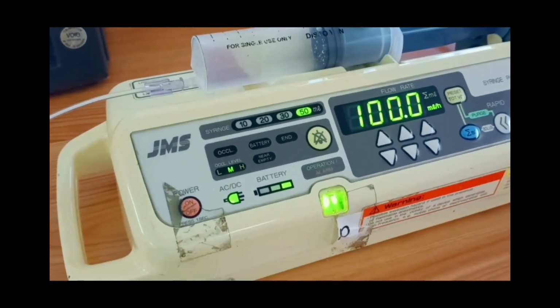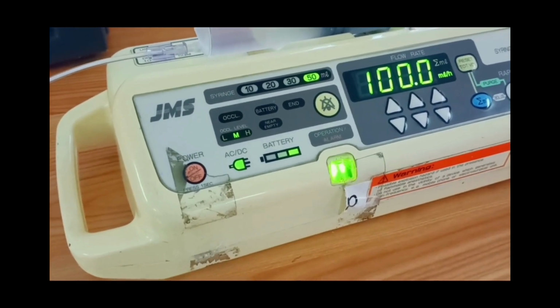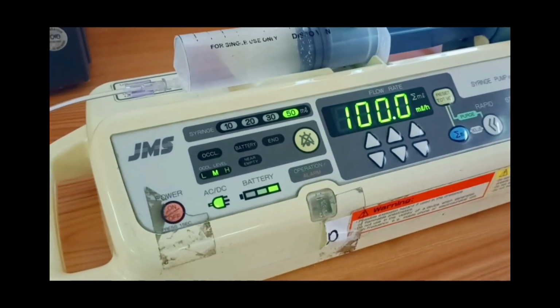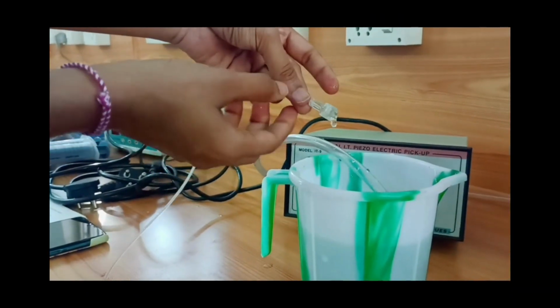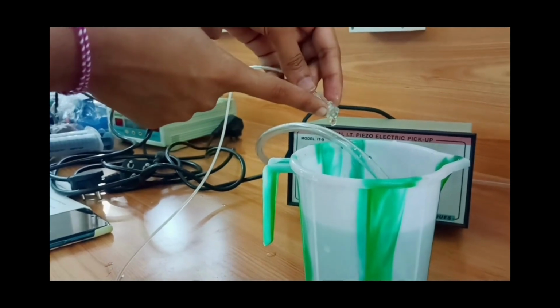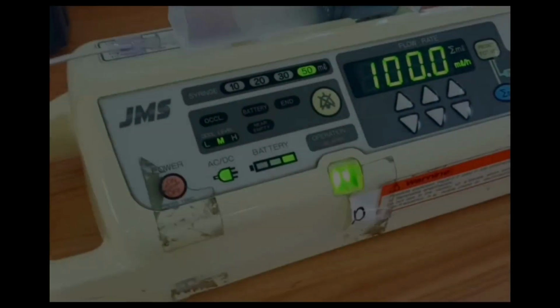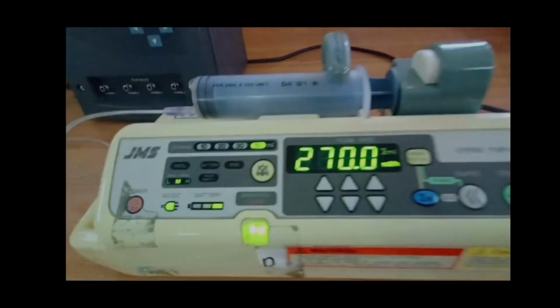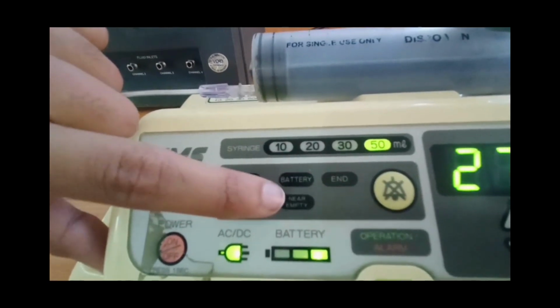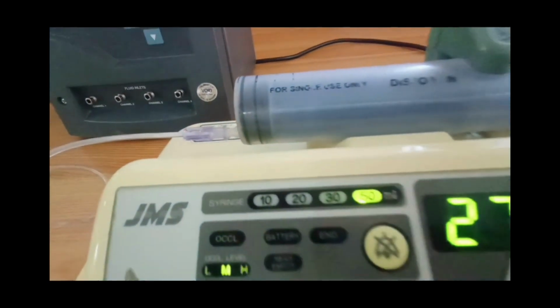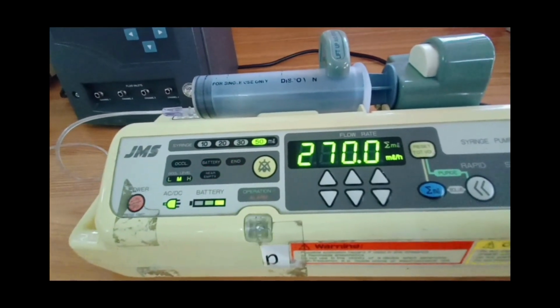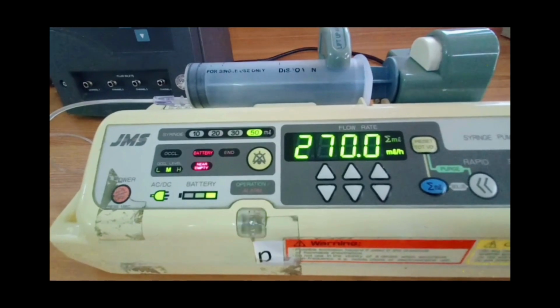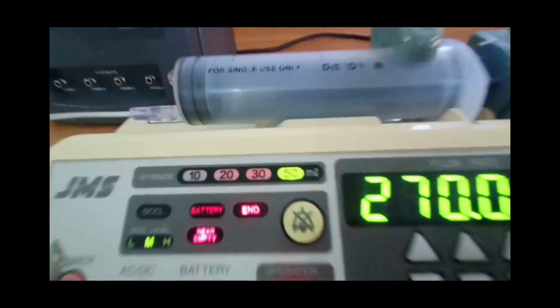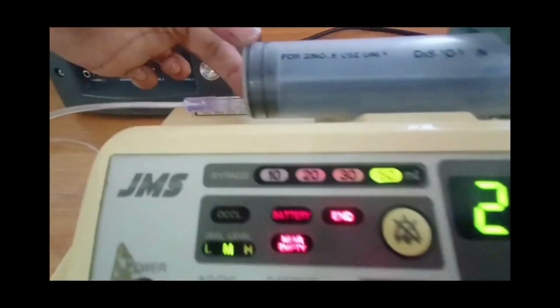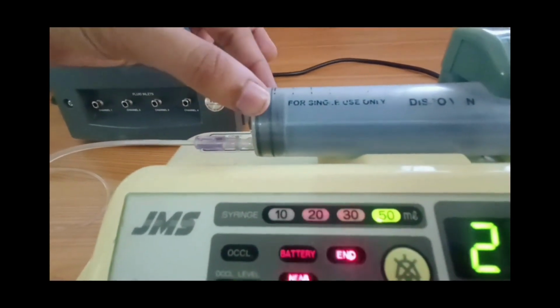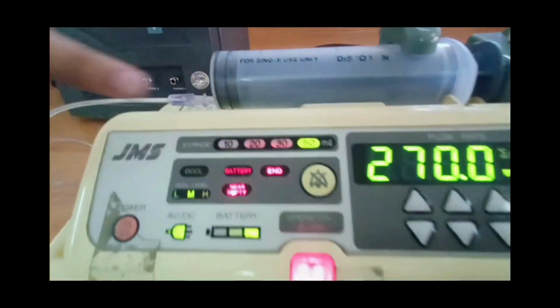You can hear some noise, that is the motor running inside the syringe pump. From the other end of the intravenous tubing, we can see that the fluid is coming out at the flow rate we have set. See here, the near empty alarm is blinking because the fluid is almost completed. Also the end button is blinking because the total fluid in the syringe has completed, so we are getting the end buzzer and the near empty buzzer.